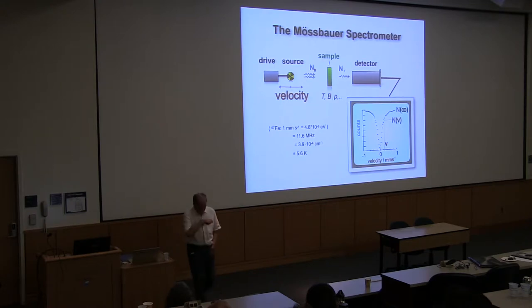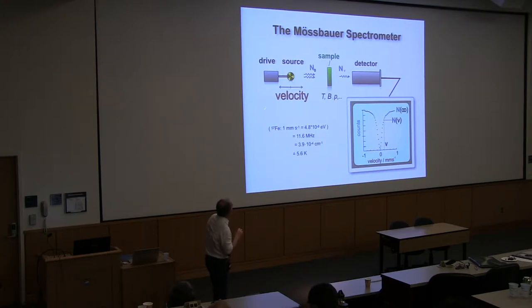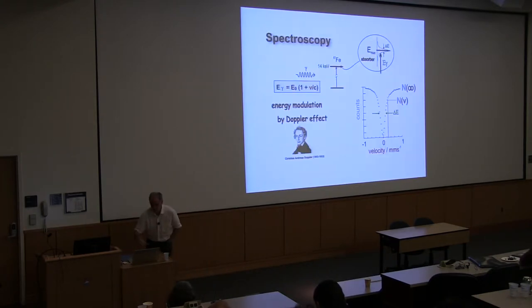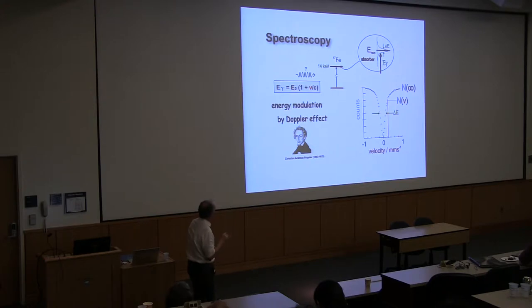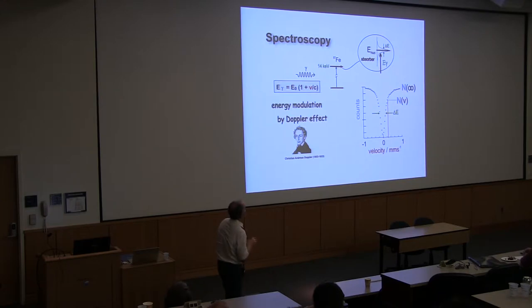Therefore a Mössbauer spectrometer is in principle a very simple instrument. We need a radioactive source. The sample is the absorber. We need only a detector to detect the intensity of light transmitted through the absorber, and we have to move the source. Then we can measure the transmission of this radiation as a function of velocity. That is the reason why Mössbauer spectra have this funny energy unit: millimeters per second. In a more microscopic picture, we modulate the energy according to the Doppler expression, where we have a modulation in units of velocity divided by the speed of light. The velocity needed to bring this setup into or out of resonance is only millimeters per second — actually a fraction of a millimeter per second.